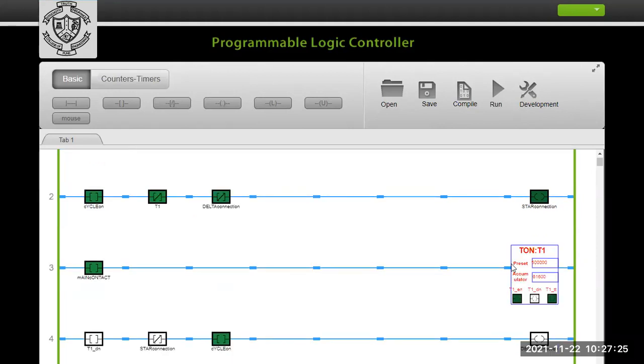And now whenever the cycle is on, it will start the main contact, means this is your physical contact, which you have just seen in the circuit diagram. And whenever the main contact is on, look, this is the one stage which is running. So whenever it is running, it will start your star connection motor, means now your motor is going to run. And whenever this main contactor is started, look, the timer also starts counting its time.